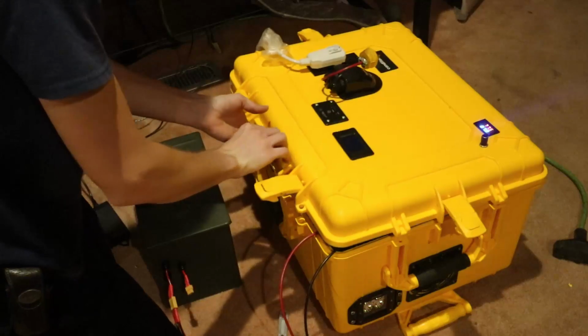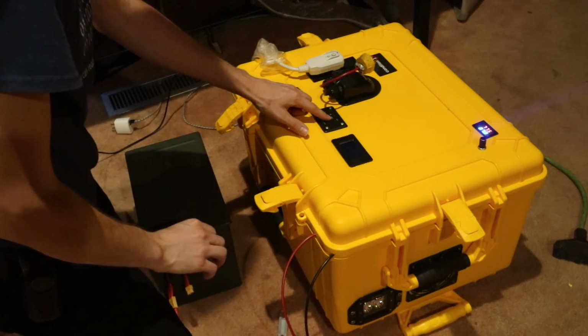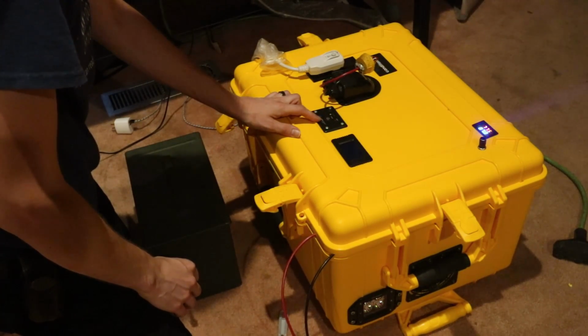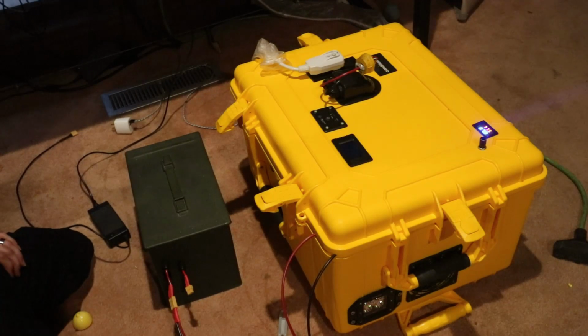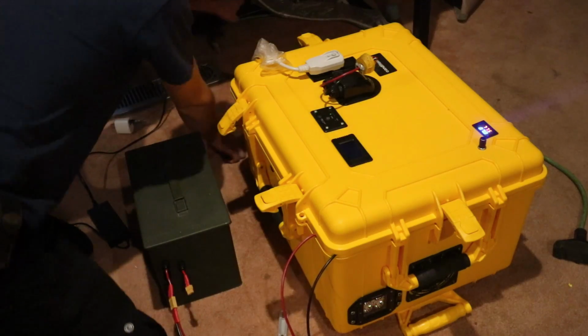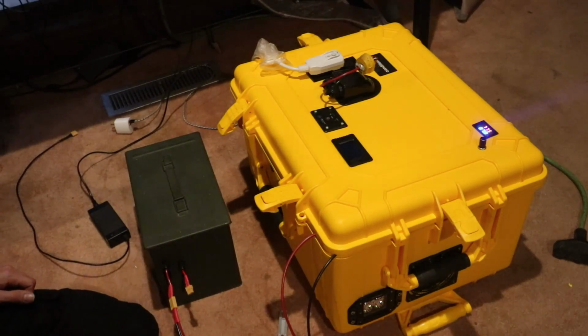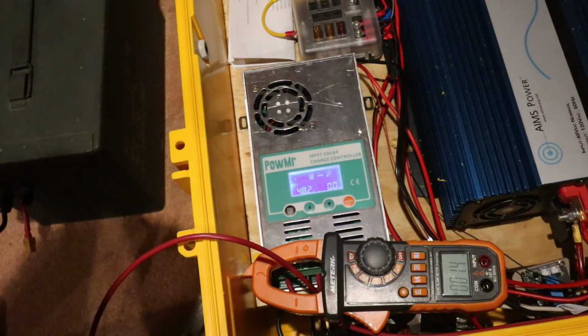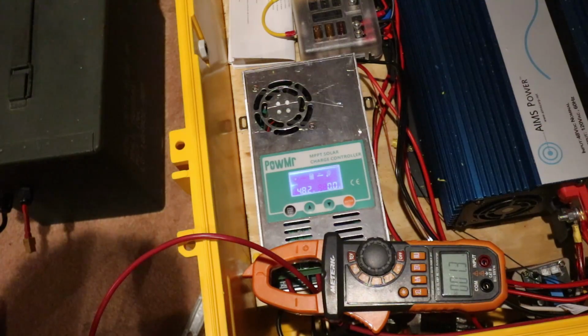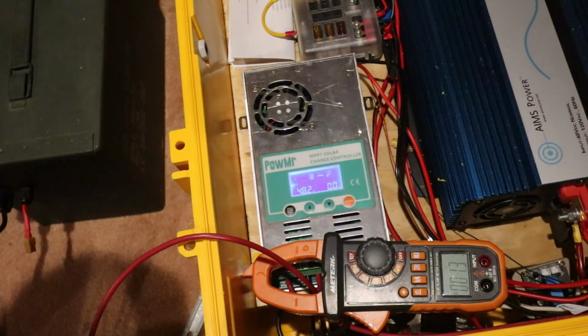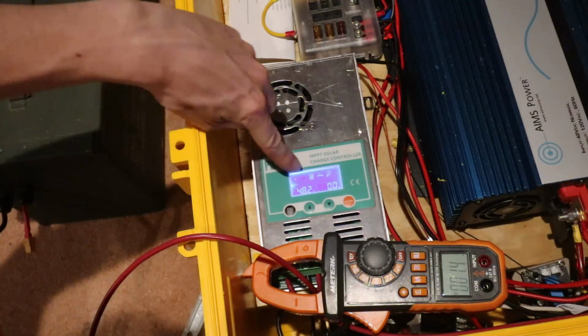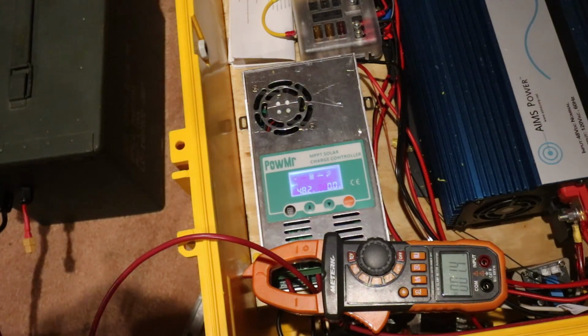Let's turn on the inverter. The AC is kicking on, it's set to 70 degrees, let me turn that down. Alright, so it's set to 64. We're seeing 1.3, 1.4 amps coming out of the battery, that's about right, maybe 60 to 70 watts. This is the voltage of the battery here, so we're at 48.2 volts.